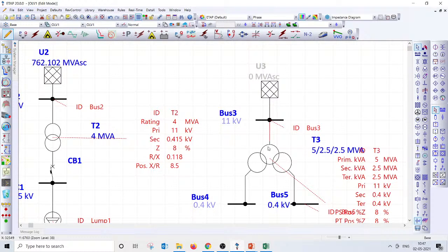Yeah, Sharinath, what factor decides the incomer to be MCCB or ACB? Answer: your short circuit withstand. MCCBs are typically available up to 800 amps, and a few manufacturers are giving up to 1600 amps, not really more than that. So anything above 1600 amps, by default it is ACB.